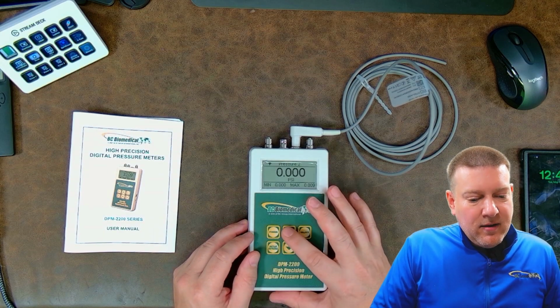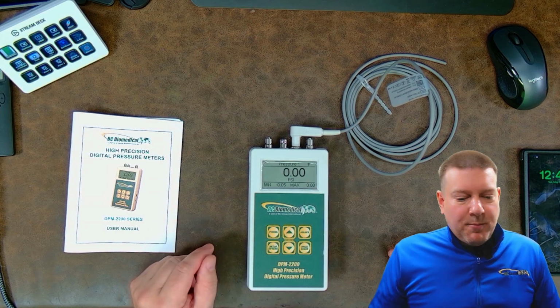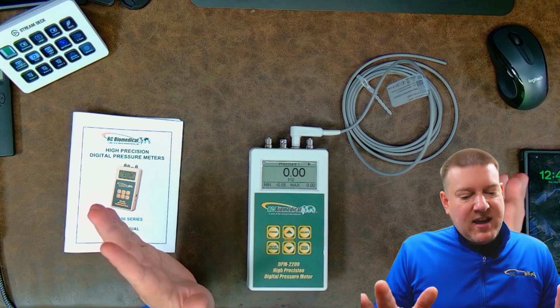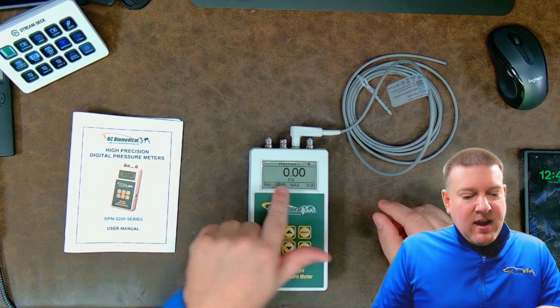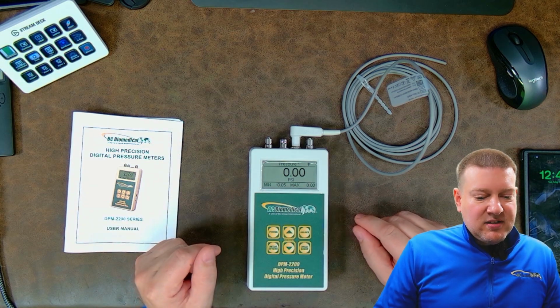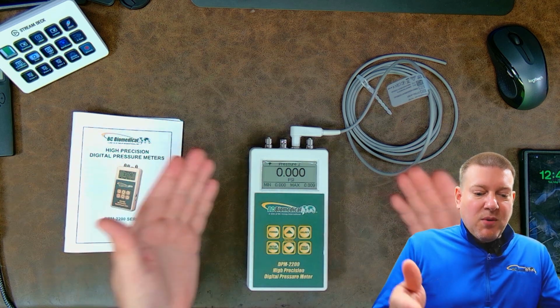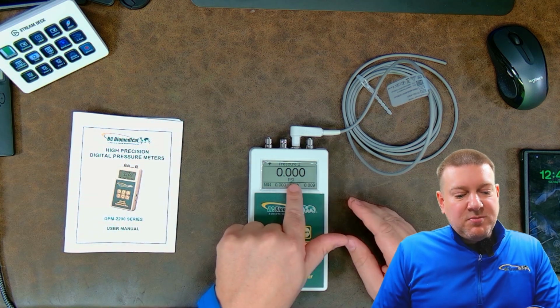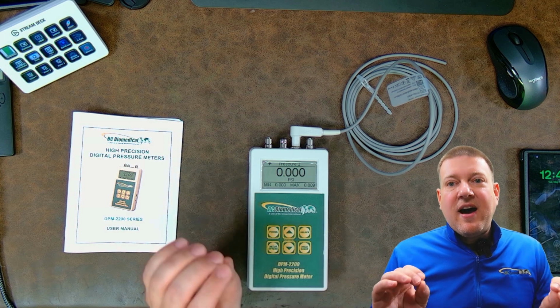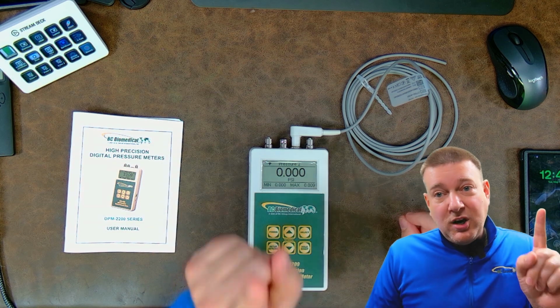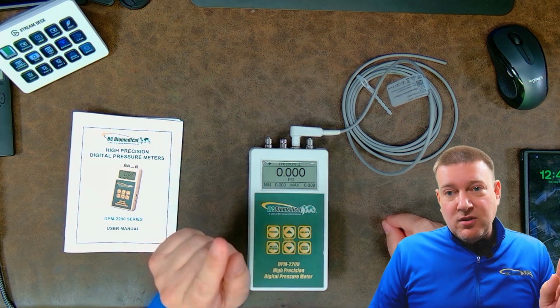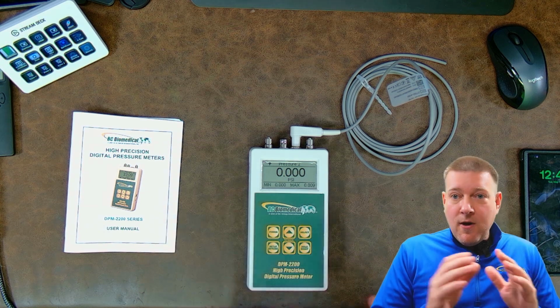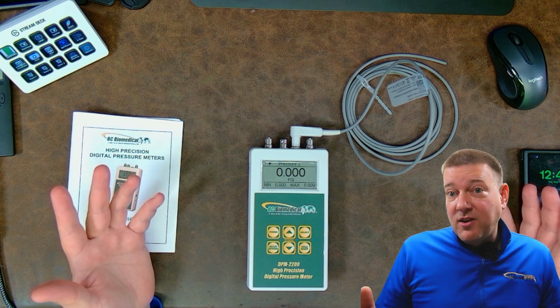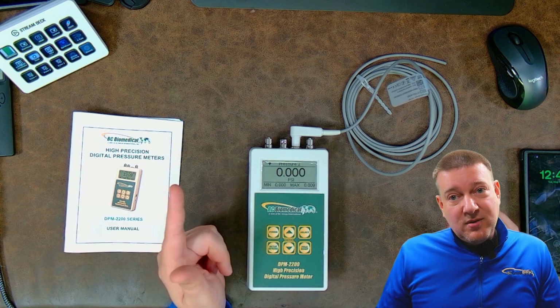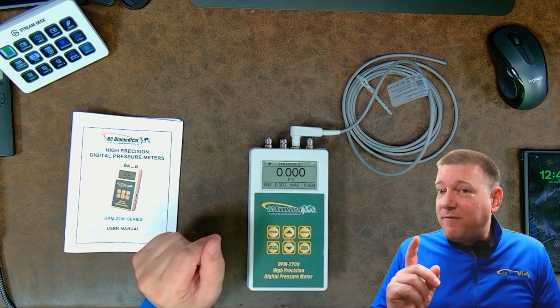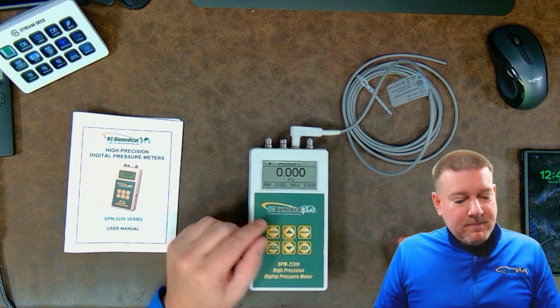Let's go back to pressure transducer number 1. Notice that this one is currently in PSI, and notice the amount of digits behind the decimal point. When we go to pressure number 2, the decimal moves over because it has higher resolution. Not as high of a pressure, but higher resolution. So if you're doing millimeters of mercury, like what you'd see on general medical equipment, pressure transducer number 2 has a higher resolution if you want to be very, very specific.